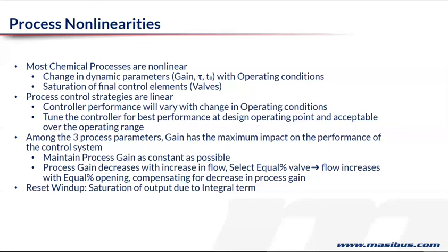So the non-linearity now sets in. Most processes and sometimes the actuators which are controlling these processes, behave in a non-linear way. And what it means is, because of that, you have set your PID at a particular set point. The same PID settings may not hold good at another set point.